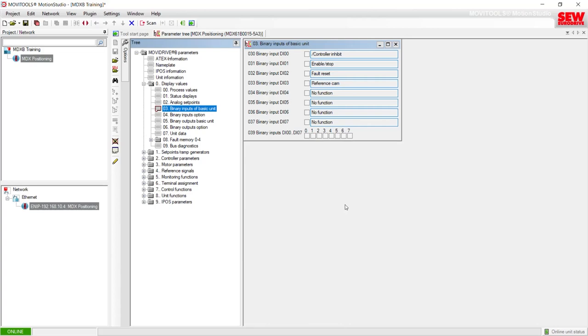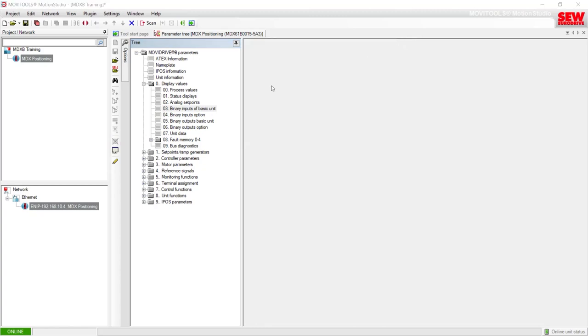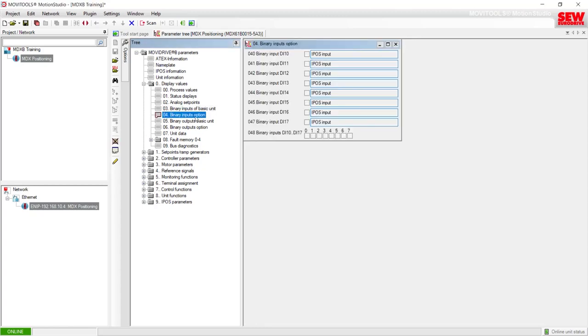The next questions ask about digital input 10 through digital input 17. This MOVIDRIVE has an expansion card for the digital inputs and outputs installed. To see that, I will close item three Binary Inputs of the Basic Unit and open up item four, Binary Inputs Option. Now I will flip the switches DI10 through DI17 and look through these checkboxes to make sure they all populate as I go through them.